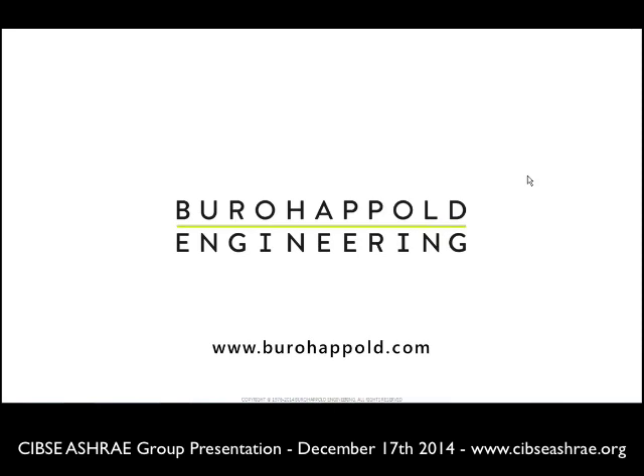I think in that instance, as I alluded to in my presentation, with such extreme climates a lot of the building services systems tend to be over-designed, because we have to meet peak performances during summer, and peak performance often does exceed published figures at the moment. If we were to design for the ASHRAE codes for the 10-year and 25-year projections, equipment would be even further over-designed.